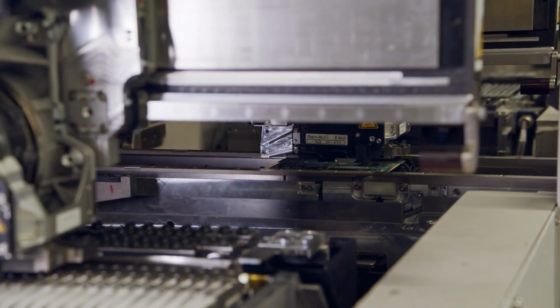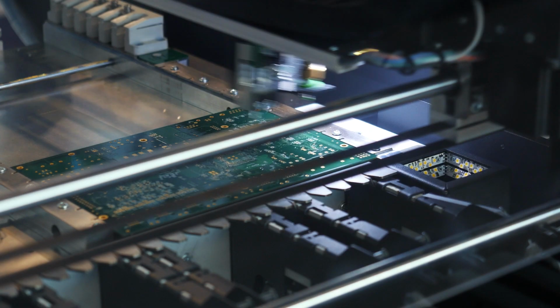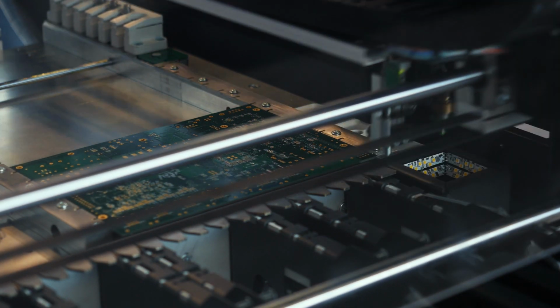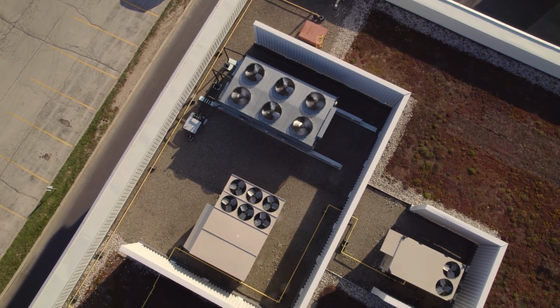High-performance compute and artificial intelligence data centers are actually increasing the electrical demand. As we've seen recently, graphic processing units versus central processing units has exploded. Data center operating temperatures are increasing. Utilizing outside ambient temperatures is becoming more and more critical. Why would I pay for cooling when it's 65 degrees Fahrenheit or below outside?